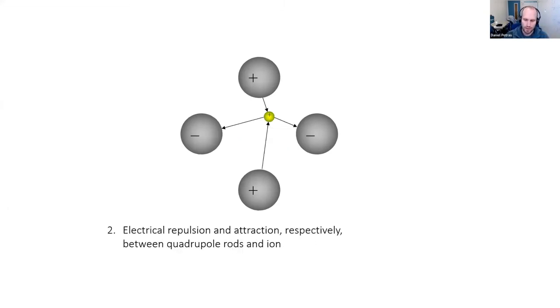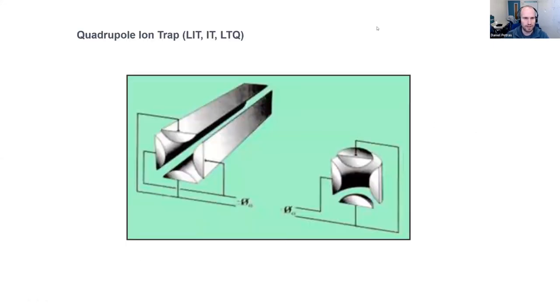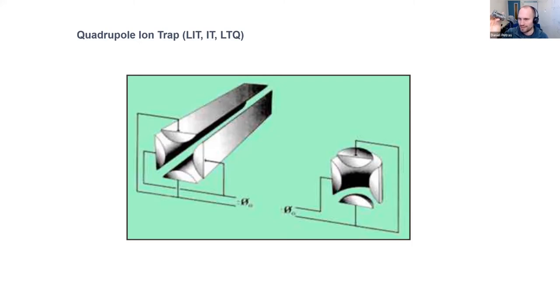The quadrupole can also be used as a trap by putting a potential at the front and end of the quadrupole — then you can not only filter ions but store them. This is a linear ion trap with four quadrupole rods taken out of an old LTQ mass spec from Thermo. The quadrupole is segmented so you can change the field at the entry and exit, using it for both separation and trapping. This also exists in a donut-shaped type of electrode — a 3D ion trap.